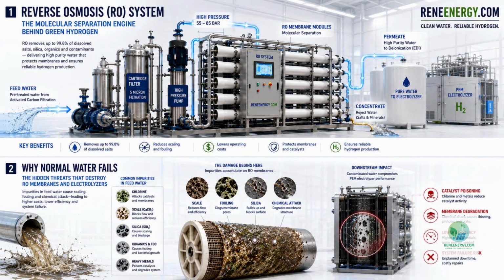These long cylindrical pressure vessels contain semi-permeable membranes that separate clean water from dissolved contaminants. The clean stream is called Permeate, and it moves toward deionization and eventually the PEM electrolyzer. The rejected stream is called Concentrate, and it carries salts and impurities away from the system. This image is important because it shows that RO is not a simple filter. It is a pressure-driven molecular separation system that protects the entire hydrogen production chain.